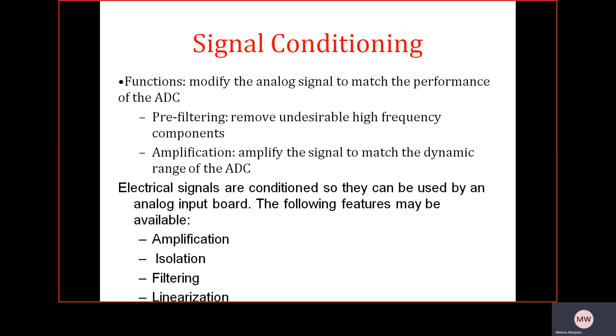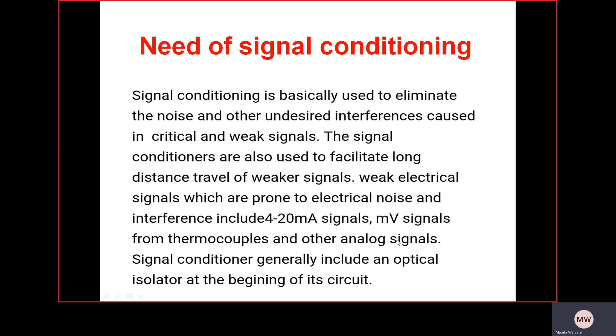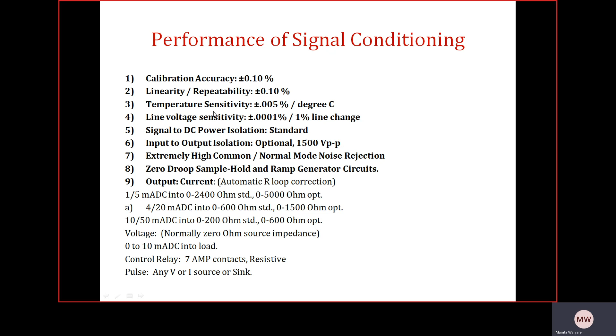There is a need for signal conditioning. It is basically used to eliminate noise and other undesired interferences caused in critical and weak signals, and to facilitate long distance travel of weaker signals. Weak electrical signals prone to electrical noise and interference include 4 to 20 milliampere signals, millivolt signals from thermocouples, and other analog signals. Signal conditioners generally include an optical isolator at the beginning of the circuit. There are various performance parameters of signal conditioning.